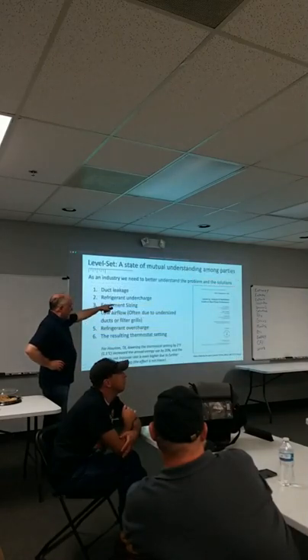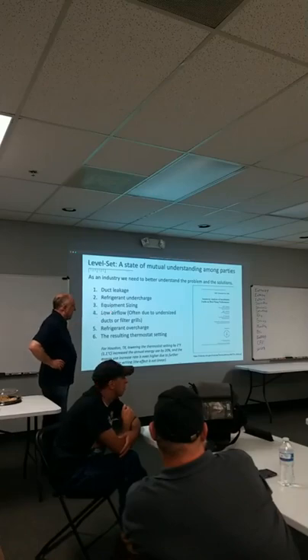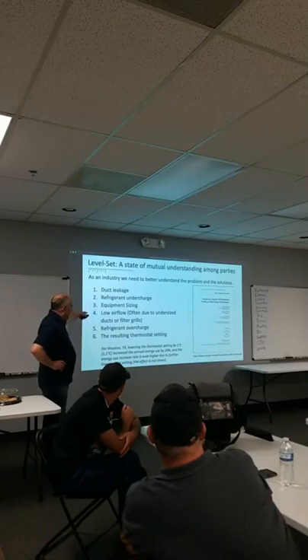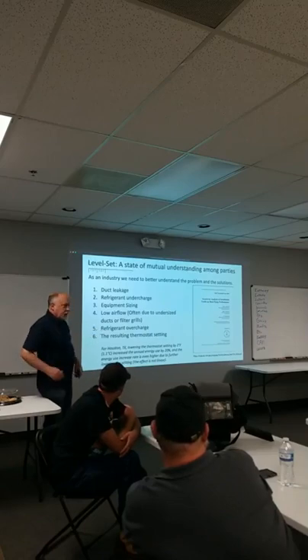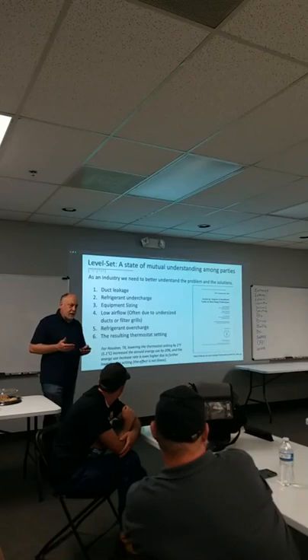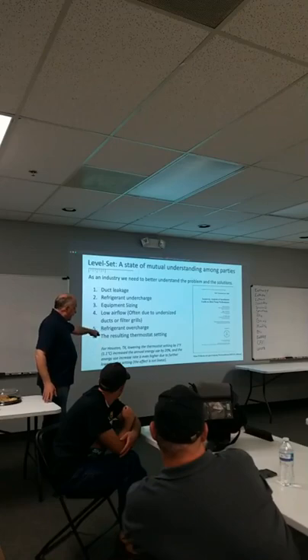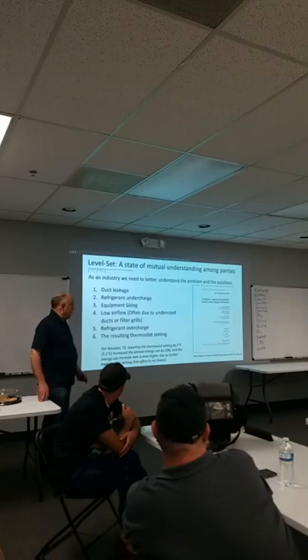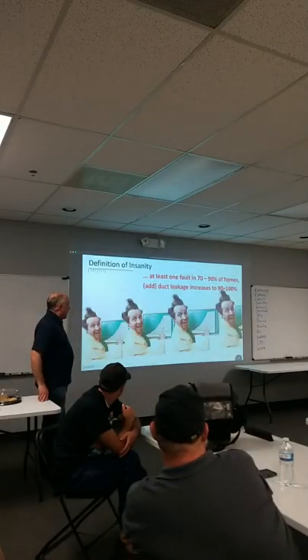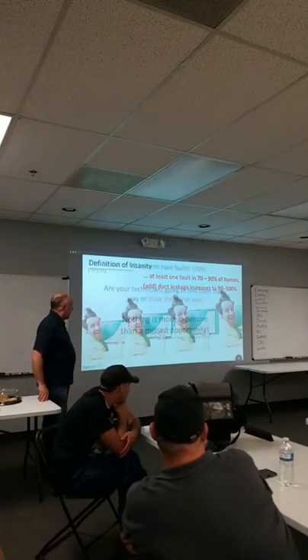Same sort of study, this one was done by NIST, a sensitivity analysis of heat pump faults. And again, they found duct leakage, refrigerant charge, equipment sizing, and low airflow. Low airflow is often due to oversizing the equipment relative to the ductwork. It's a very common problem. Also refrigerant overcharge and the resulting thermostat setting. Just to put this in perspective, the only control a consumer has is the thermostat. So if they're not comfortable, they're gonna turn the thermostat down. Just taking it down 2 degrees in Houston, Texas, increases your energy bill by about 20%, right? So it's just sort of insanity. We're doing the same thing over and over again, expecting a different result.